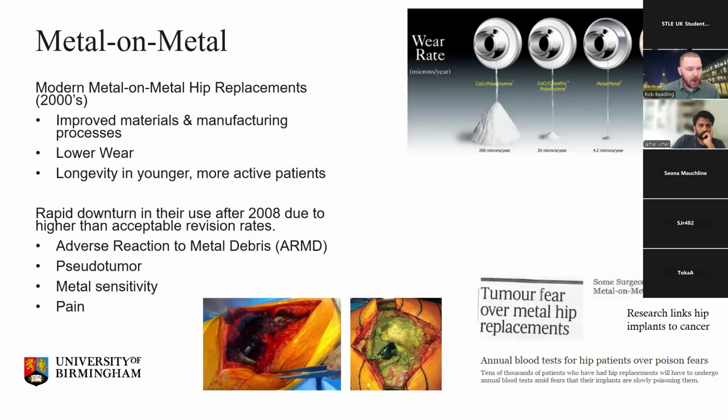And again, they focused on this wear rate. Compared to a polymer device, the wear rate from a metal-on-metal was orders of magnitude lower. But after around 2008, they were only predominantly put in during the early 2000s, these things started falling out left, right, and center.